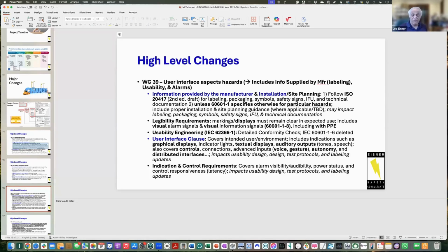There is a pretty significant section in the standard that we're developing. Some came out of third edition amendment 2, but we've added to that list. Then there's also installation requirements that we've developed, which I was on the sub team that worked on. And that's a fairly extensive list, but it's only going to be specific to your device. You're going to pick from a list and apply what applies to your device. And you may add to that. This is just sort of a suggestion list.